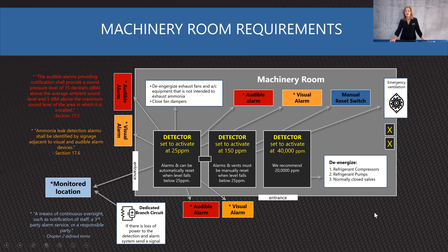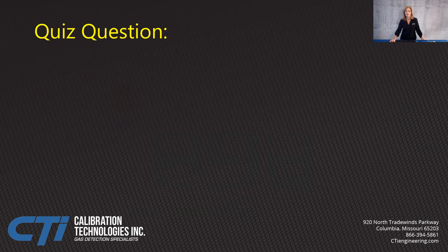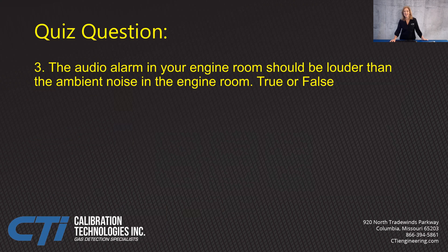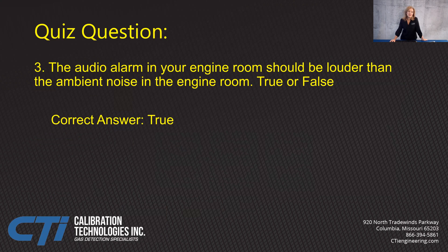Here is a diagram showing all of your machinery room requirements. Quiz question: true or false — the audio alarm in your engine room should be louder than the ambient noise in your engine room? That's true. There's no point in having an alarm you can't even hear. It has to be 15 decibels above your ambient noise, or five decibels above your maximum noise.